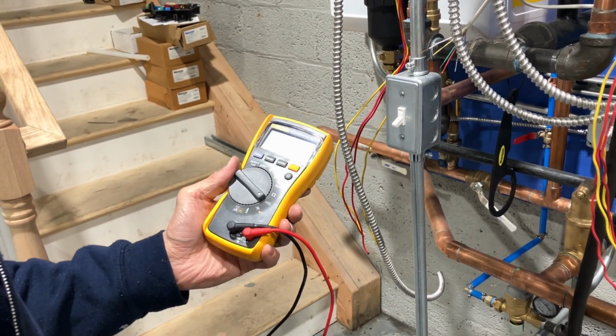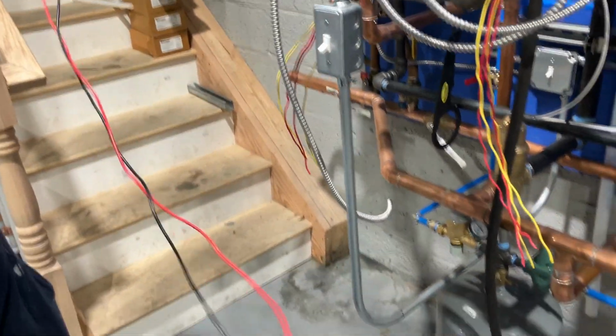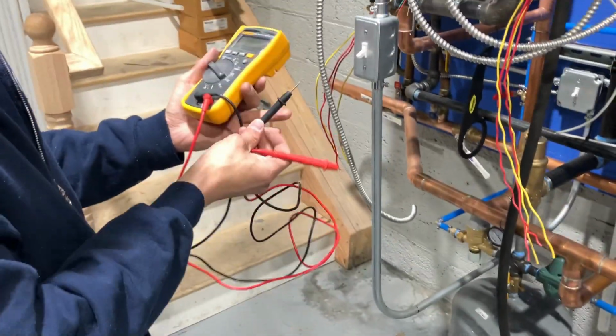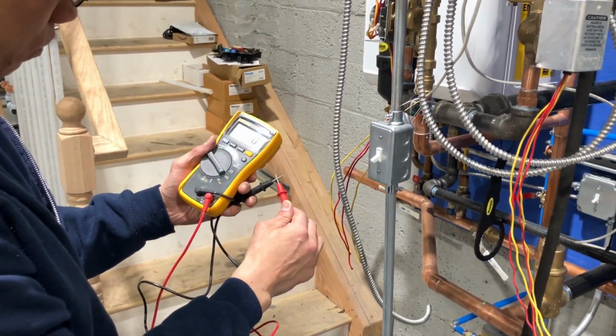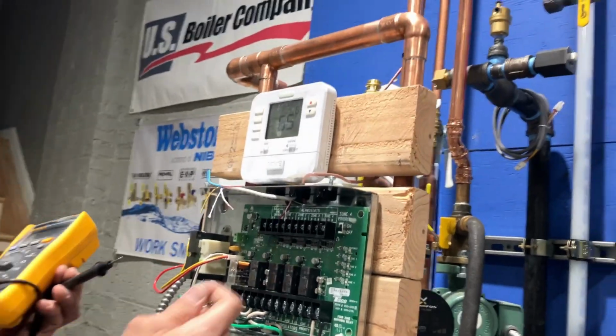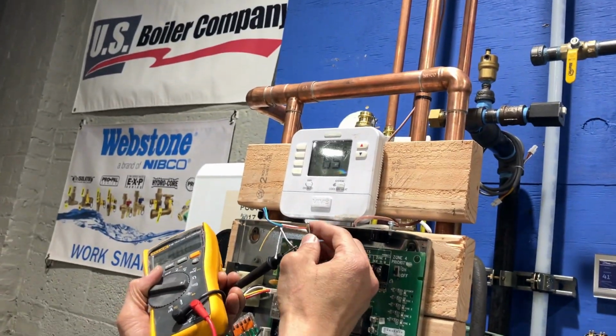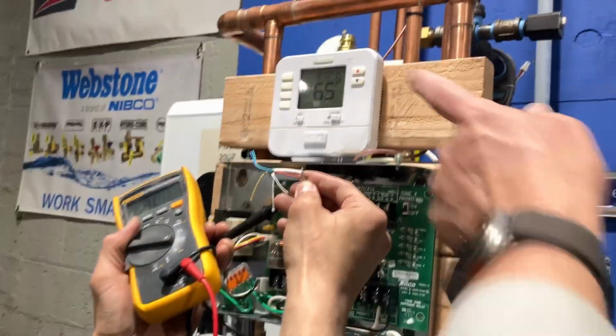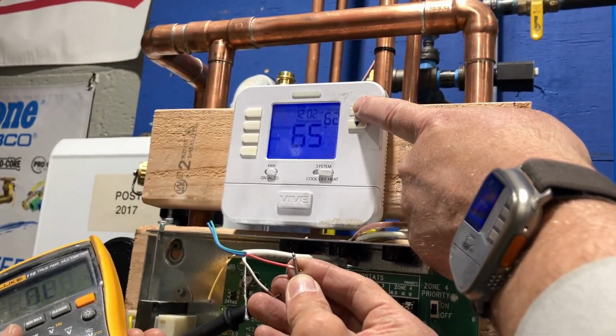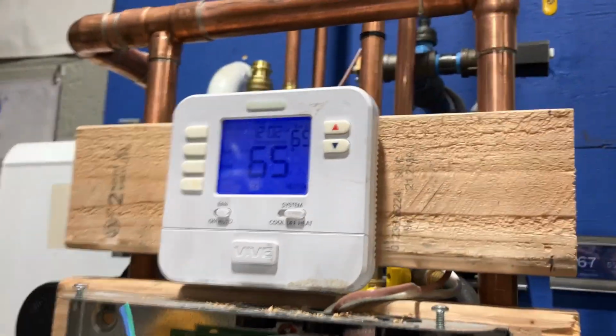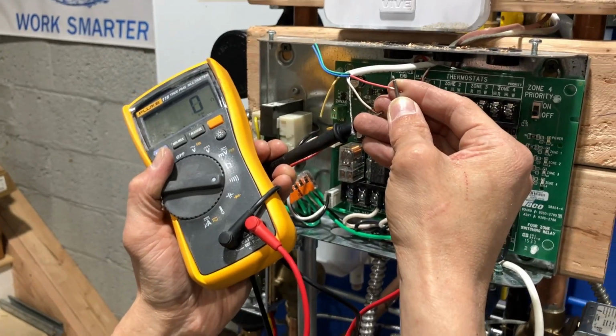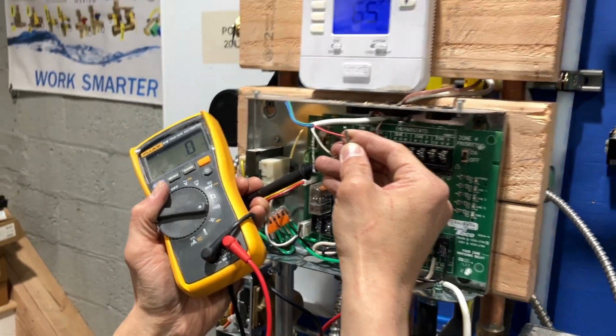All right, let's set that for continuity. Great. And it is also a very good habit to touch the two leads together to make sure that we are reading continuity. Perfect. We hear that little beep. Now, R and W, touch the two wires with your two leads. We have no continuity. We're going to raise up the temperature. Heard that little click? The second you heard that click, you have continuity on those two wires.